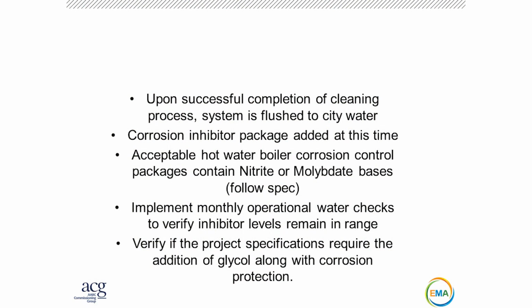Once the system is installed and operating, like it says here, upon successful completion of the cleaning process, the system is flushed to the city water, and chemicals are added. If it's a hot water boiler, corrosion control packages include nitrites or molybdates. And make sure you do the daily tests or monthly tests at least. When I was an operator, we would do our tests every shift. And that way we made sure we were on top of things, that there were no problems. Like I said, working with Phil's previous boss, he was a great guy, very knowledgeable. He loved to share information. He was very informative. If you have a manufacturer's rep or a contractor, use them to your advantage.